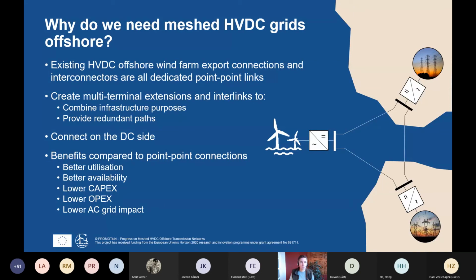The current point-to-point HVDC system building paradigm persists due to many technical, legal, regulatory, and system planning reasons. First of all, from a technical perspective, novel, previously unused technologies are necessary to build meshed HVDC networks. The converters and offshore wind farms need to be controlled to guarantee stable operation in both steady state and dynamic conditions. The power needs to be equally distributed among all the converters, also during changes in generated wind power or in case of faults in either the HVDC network or in one of the neighboring onshore AC networks.